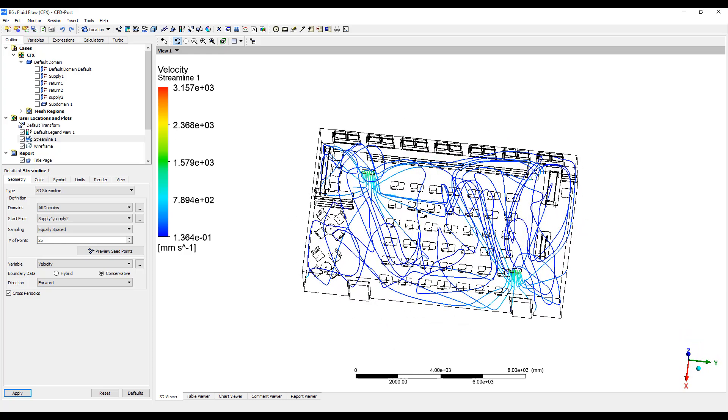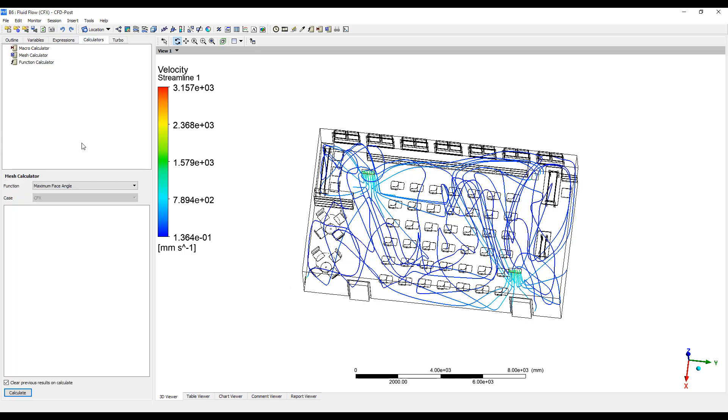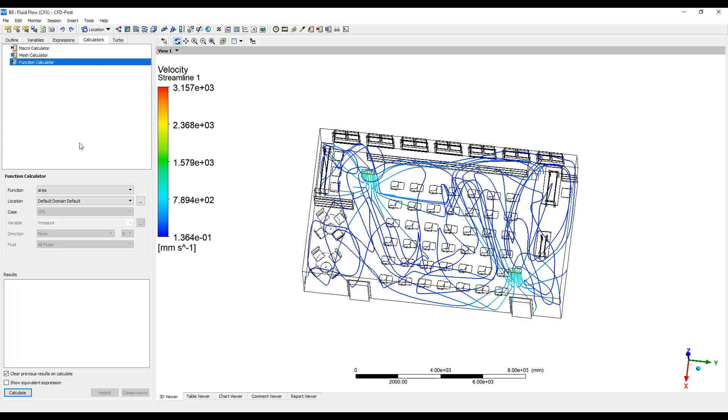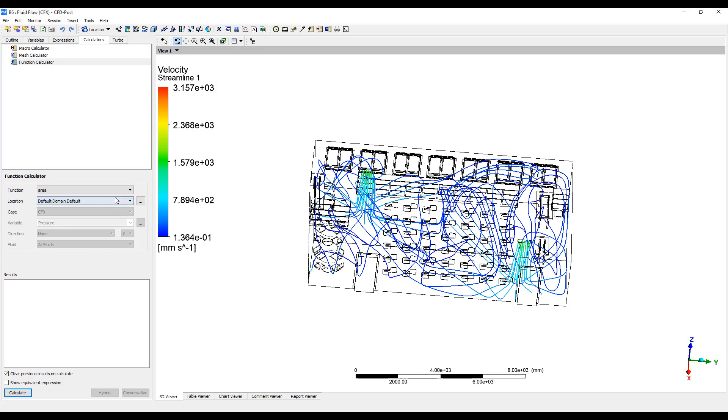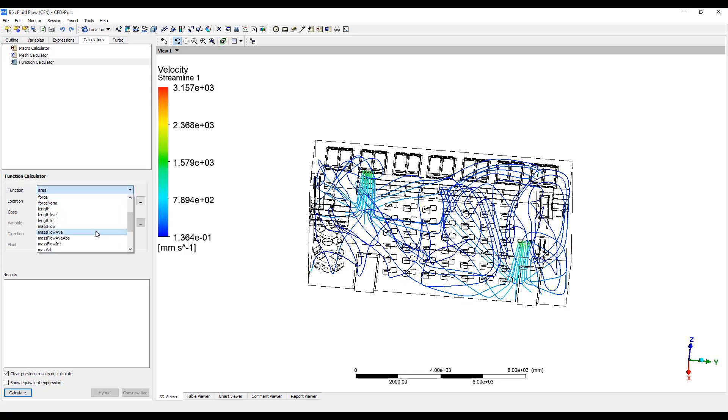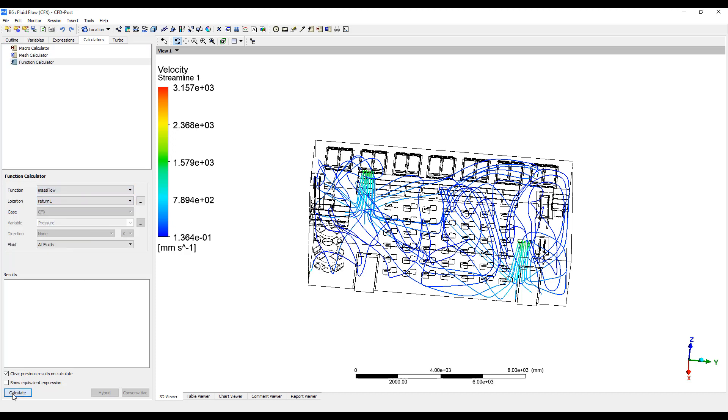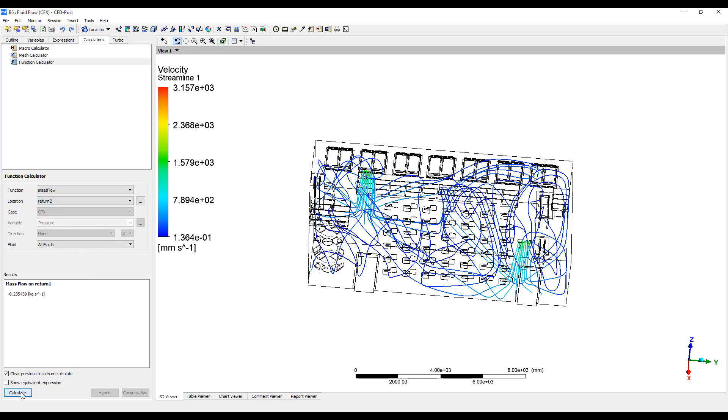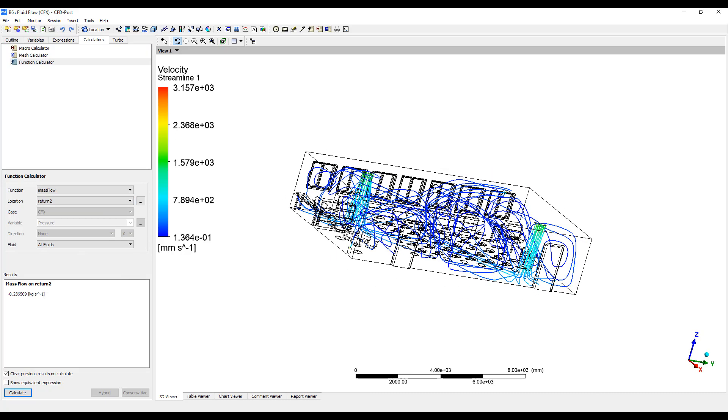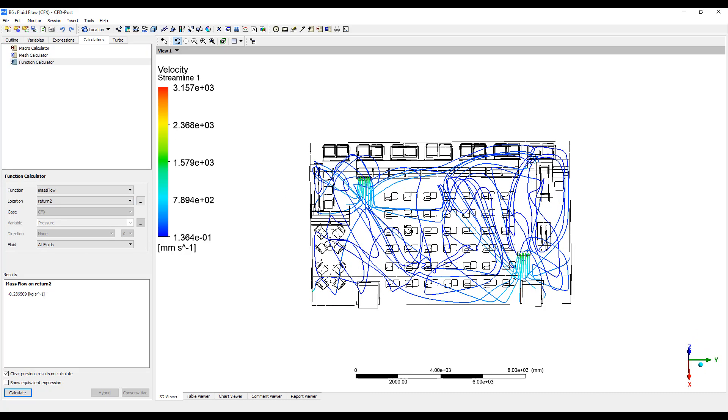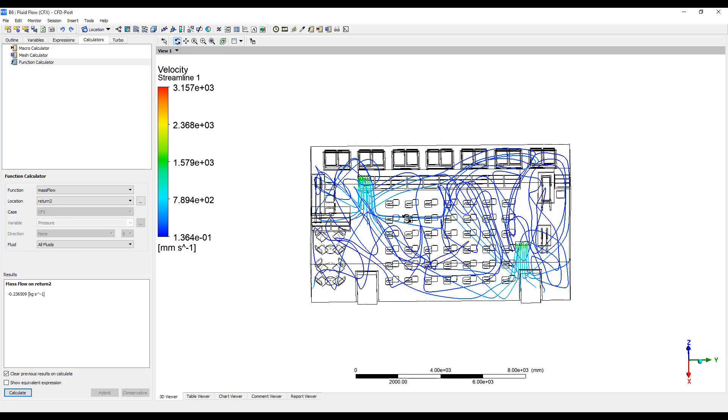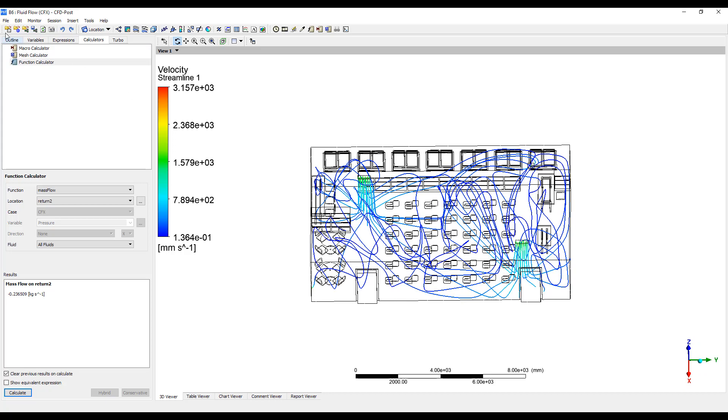You can see a different amount of flow going through each of the returns. We can calculate how much air is getting into each return. We can count the mass flow in return one, 0.235, and return two. So pretty much the same amount, equal amount of air going through each of the returns.